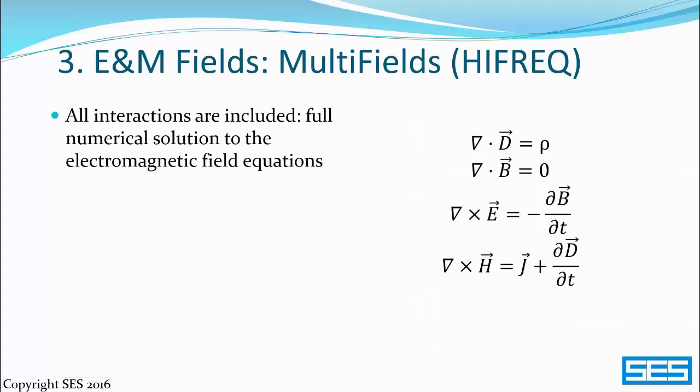Thus far, we've focused mostly on conductive coupling, the idea of current flowing in the soil and along buried conductors, with only a passing mention of inductive coupling that we mentioned in the context of fault current split calculations. The next way to improve the grounding model is to solve the electromagnetic equations completely in order to get all electromagnetic interactions represented. This is what can be done with MultiFields via the HIFREQ module.